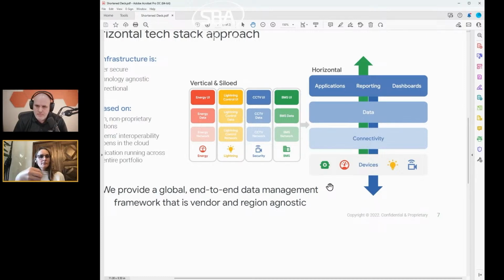almost dynamically updated. So the concept is you start with a manual process, and as we go, we're automating this process more and more. And then you have to be able to validate this model against your as-is building, right? How do you know? Did you model something that actually doesn't exist in your building? Is your model including all the devices we have in the building, or is it including extra devices that are not in the building? How do you validate that?